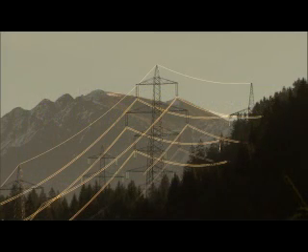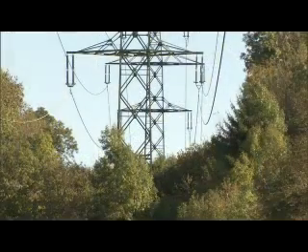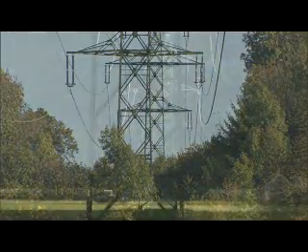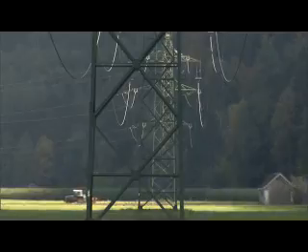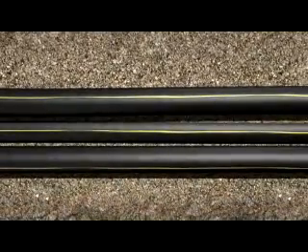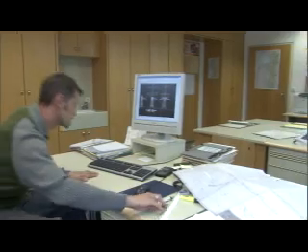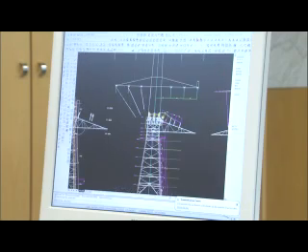Until now, the K factor has been calculated from system data. This calculation is problematic if the topography of a line is complicated. Parameters such as the height of the conductors above the ground and the soil resistivity can have significant influence. For older cable installations, some of the parameters required in the calculation may simply be unknown. Due to the large number of different parameters required and the difficulty in obtaining data, the calculation can be error prone.